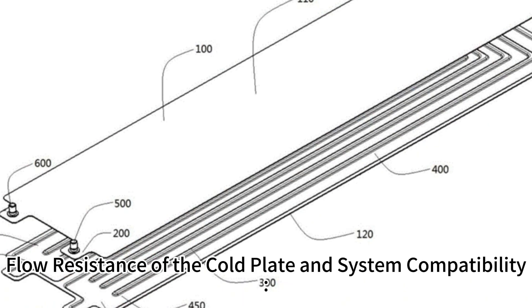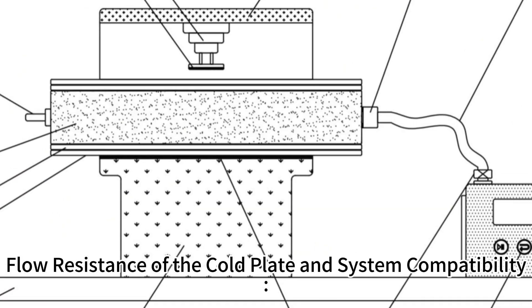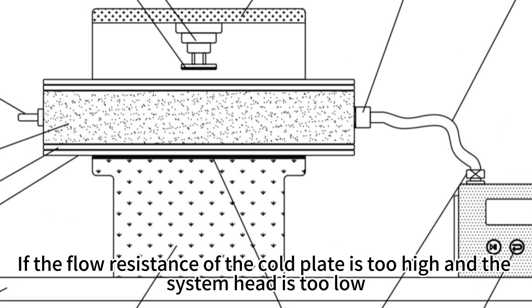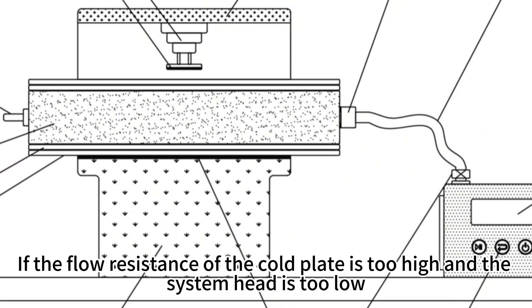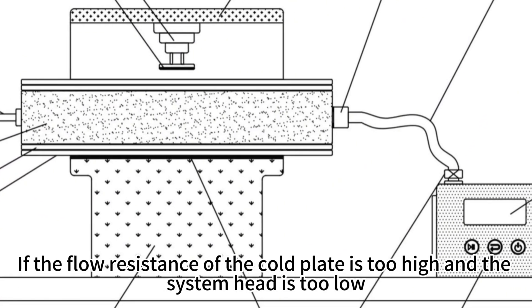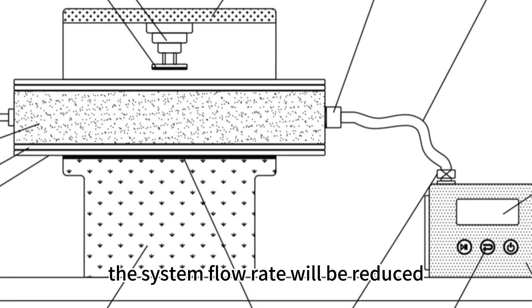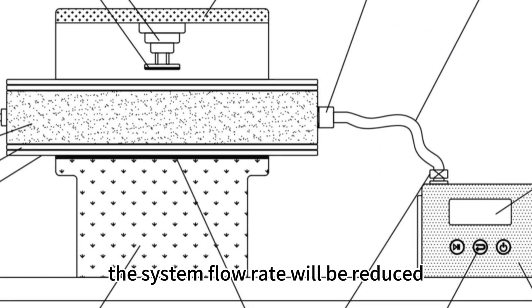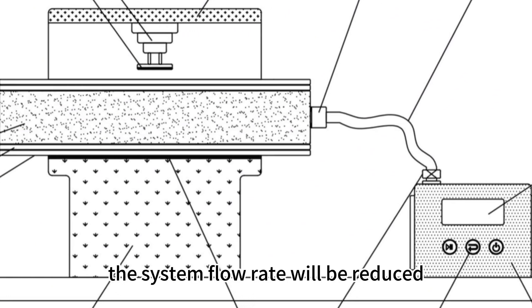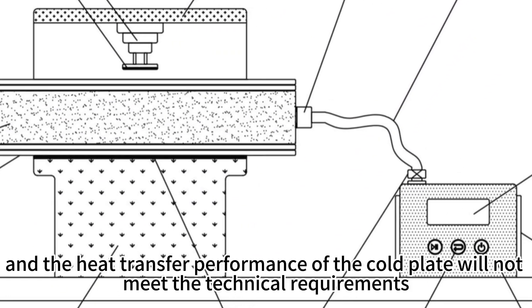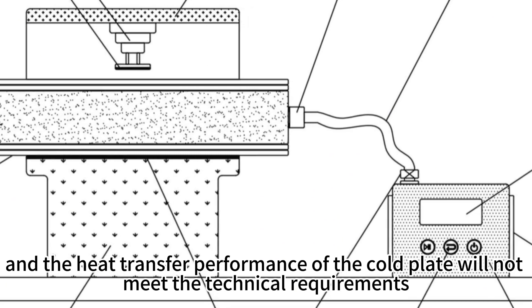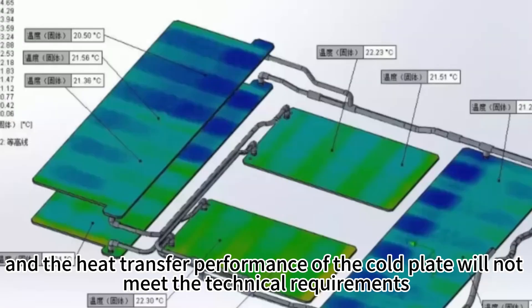Flow resistance of the cold plate and system compatibility. If the flow resistance of the cold plate is too high and the system head is too low, the system flow rate will be reduced, and the heat transfer performance of the cold plate will not meet the technical requirements.